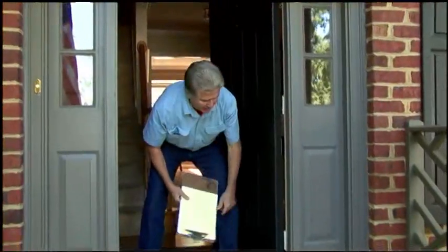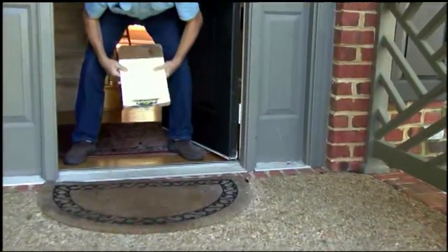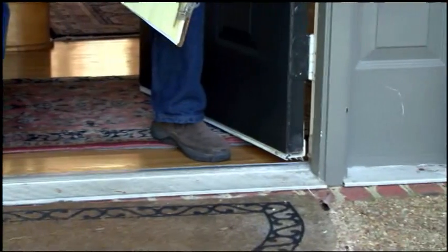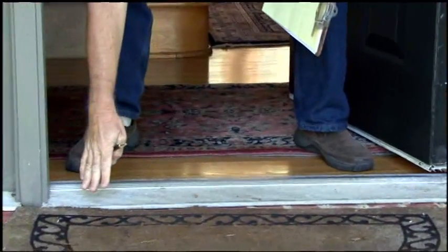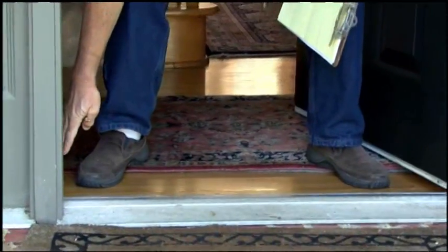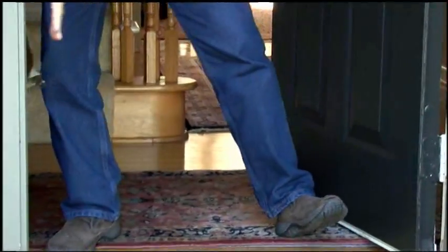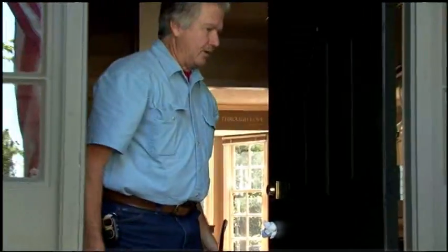On doors, there's little pads at the corner, one here and one that's missing here. So there'll be daylight coming through here, and there'll also be a draft moving through here too. So we'll have outside air going into a conditioned space, and that leads to higher energy usage.